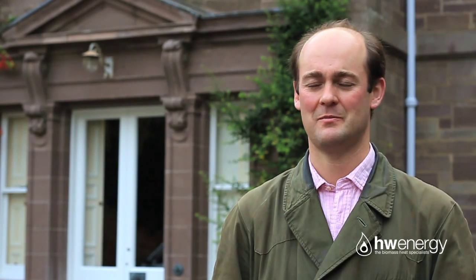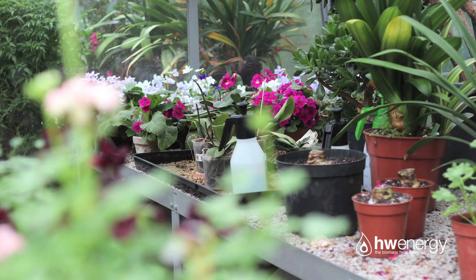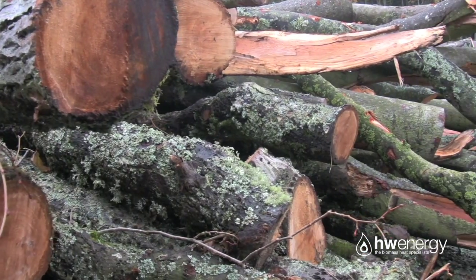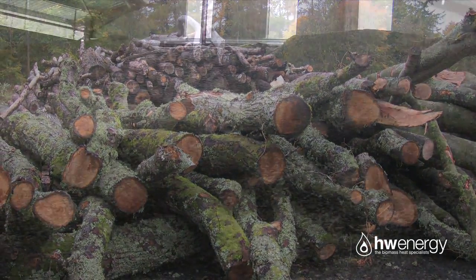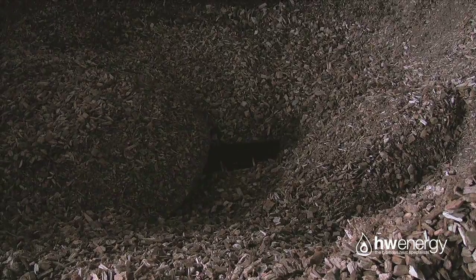Roughly speaking, the grant is about £35,000 a year, obviously depending on usage, and the oil cost for this house plus the other 15 properties that the boiler is connected to would equate to about £50,000 a year. Because we produce our own wood chips, our cost of chip is lower than it might be otherwise, so it costs us about £30,000 a year fully loaded in terms of wood chip cost. That provides an overall saving of about £20,000 a year, though there are obviously other things one would need to look at to provide a completely fair reflection on the overall savings.